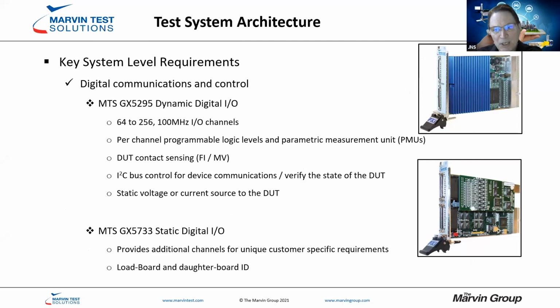The per pin parametric measurement unit, or PMU, and it's essentially a SMU on a pin, is typically used to verify connectivity prior to applying power to the device to minimize the potential for damage, ensuring that all the connections are in place in all the various power and return lines are making good contact. And the load board and daughter board IDs are also verified using these digital interfaces as well.